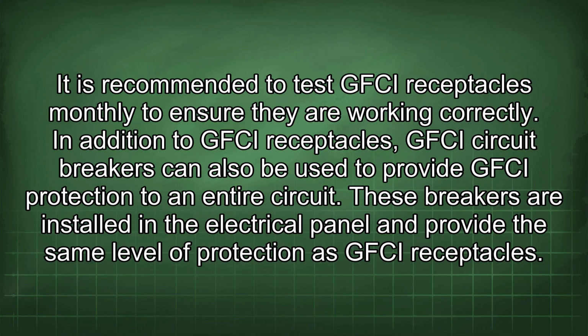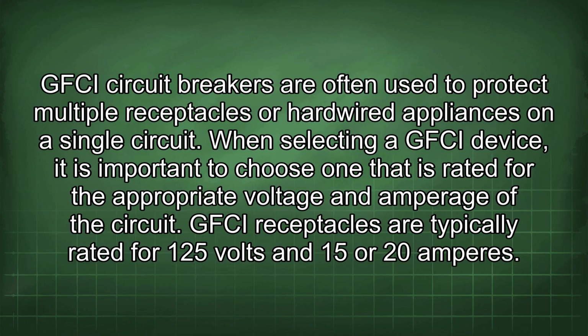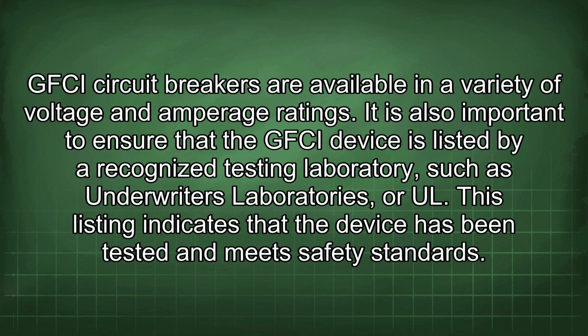In addition to GFCI receptacles, GFCI circuit breakers can also be used to provide GFCI protection to an entire circuit. These breakers are installed in the electrical panel and provide the same level of protection as GFCI receptacles. GFCI circuit breakers are often used to protect multiple receptacles or hardwired appliances on a single circuit. When selecting a GFCI device, it is important to choose one that is rated for the appropriate voltage and amperage of the circuit. GFCI receptacles are typically rated for 125 volts and 15 or 20 amperes. GFCI circuit breakers are available in a variety of voltage and amperage ratings.